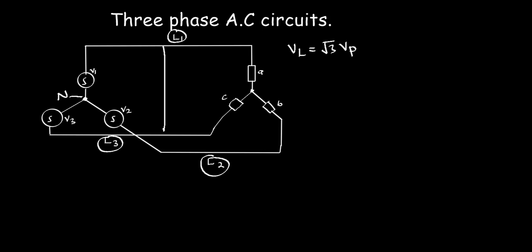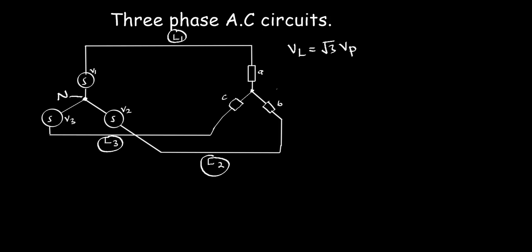I can measure the voltage between L1 and L3 — that is termed as a line voltage. Similarly, I can also measure between L1 and L2, or L2 and L3. They are all termed as line voltages. So the line voltage is equal to the square root of 3 multiplied by the phase voltage.